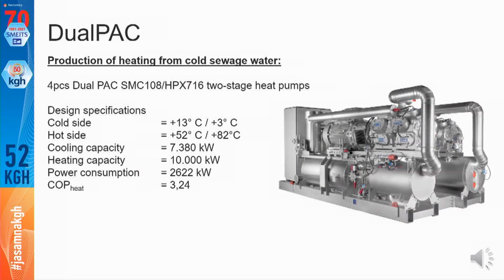Another one, this is the type of system Armin showed. It's a DualPAC which can lift the temperature from the cold side up to 82 degrees in this case, and it provides around 10 megawatts of heating capacity with a COP around 3, which is acceptable in this part of the world with the energy prices we have. With growing energy prices, it becomes even better for heat pumps compared to other fuels.